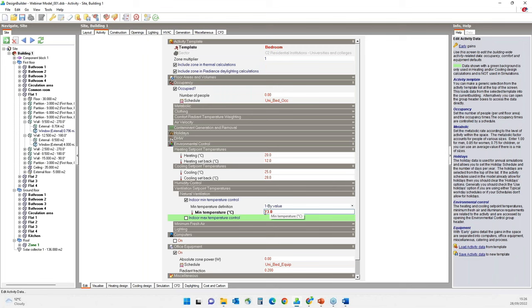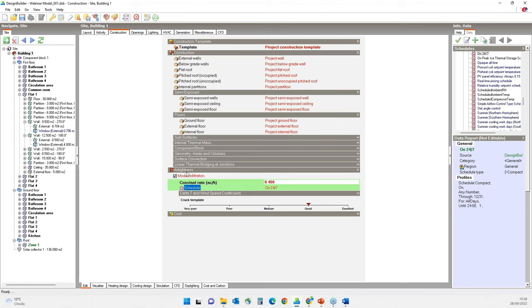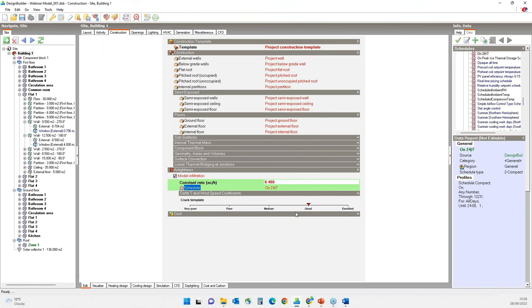Going to the activity tab: we have set the natural ventilation temperature to 23 degrees Celsius and I will leave it as it is. On the construction tab, under the air tightness header, note that the constant infiltration rate has a green background and is only used in heating and cooling design calculations. For calculated natural ventilation, infiltration is defined using the crack template. You should check that the crack template setting reflects the age and type of building — most new buildings should be set at least to good.